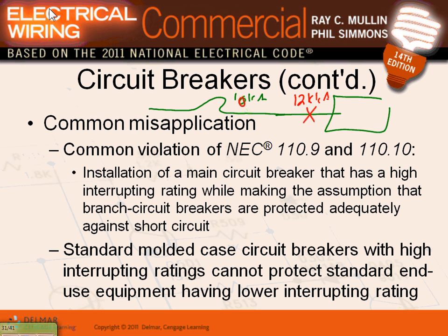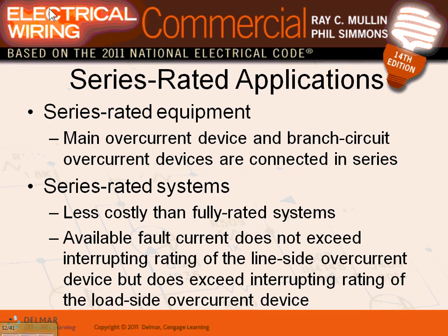And the other thing is, if your breaker has a very high interrupting rating, then also it doesn't protect you. If it has extremely high, it wouldn't trip before the equipment burns. So you have to match it really. If you have a 12, you need 10. You don't need 65. So you have to kind of have the optimum design for this baby.